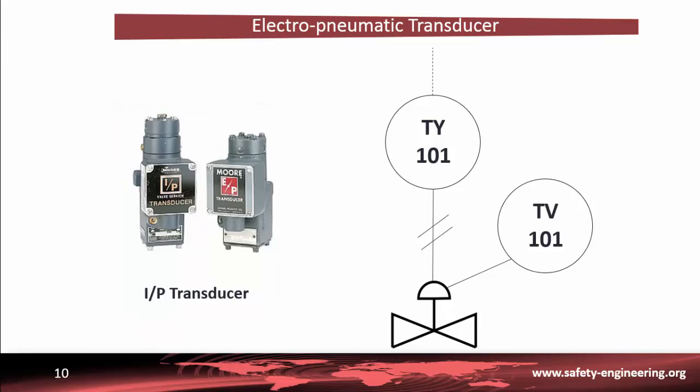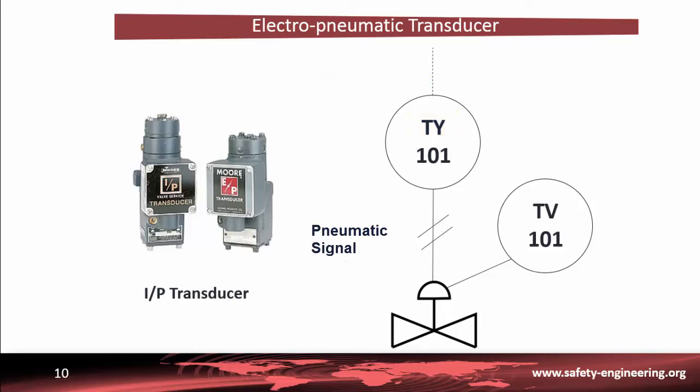The figure shows an example of a P&ID diagram. The tagging convention for the IP transducer is the letter Y. TY means an IP converter for temperature regulation. The input of this device is an electrical signal, shown by a dotted line, and the output is a pneumatic signal, shown by a slashed line.